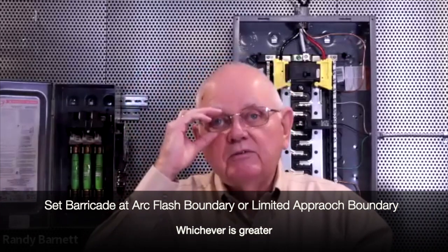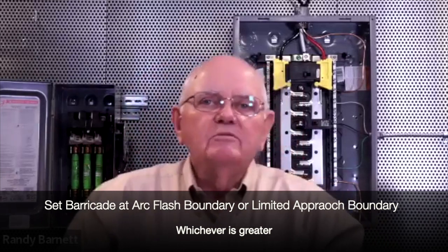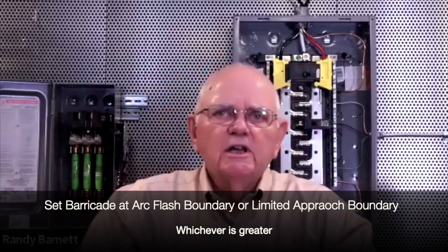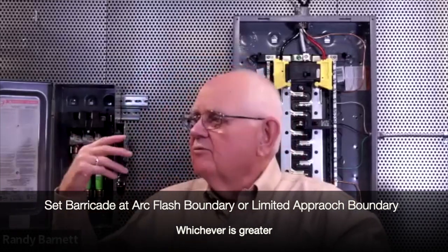I always tell people to remember, that's only the minimum distance, okay? That's only the minimum. If my limited approach boundary is 3 feet 6 inches and my arc flash boundary is 7 feet, maybe I decide, you know what, I'm going to set my barricade tape up at 10 or 15 or 20 feet or block the room off, whatever it is I'm doing. I want to keep people safe. So those are my minimum requirements.